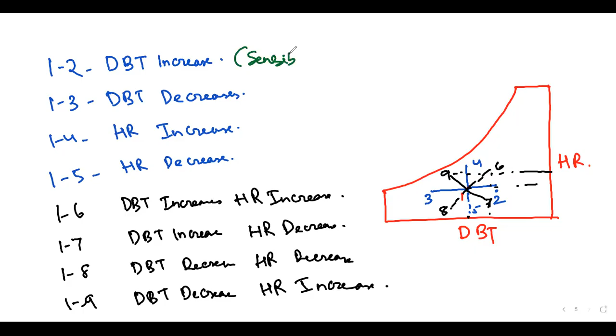If your dry bulb temperature decreases, then sensible cooling. Correct? If your HR increases, you will have humidification. If humidity ratio decreases, then dehumidification. Now here, dry bulb increase means sensible heating, plus HR increase means humidification. Dry bulb increase with HR decrease means sensible heating plus dehumidification. Dry bulb temperature decrease means sensible cooling, HR decrease means dehumidification. For 1 to 9, dry bulb decrease means sensible cooling plus humidification, right?